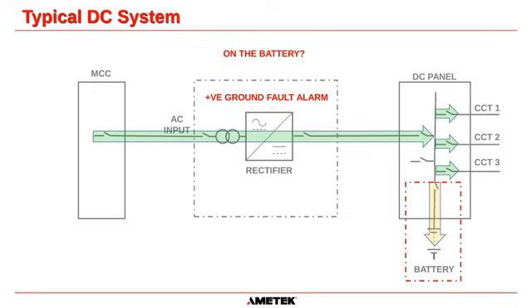The other thing that I've seen is the cables that go to the battery, they're usually tie wrapped very tightly to either cable tray or the battery rack stanchions or something like that. And what can happen is if there's any burrs on the cable tray or on the battery rack and there's any kind of vibration in the system, that can poke through the insulation eventually and can cause a ground fault on the battery. Okay, they're really the only two ways you can get a ground fault on the battery.